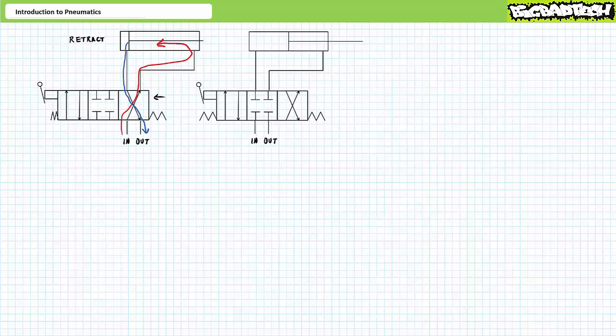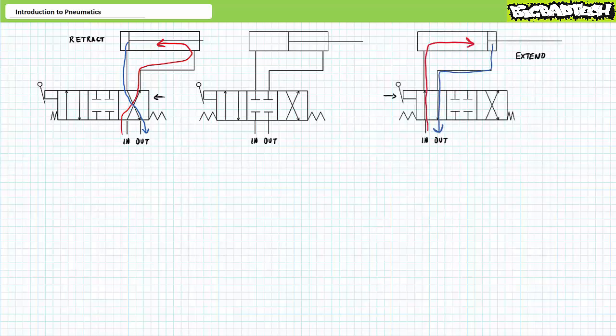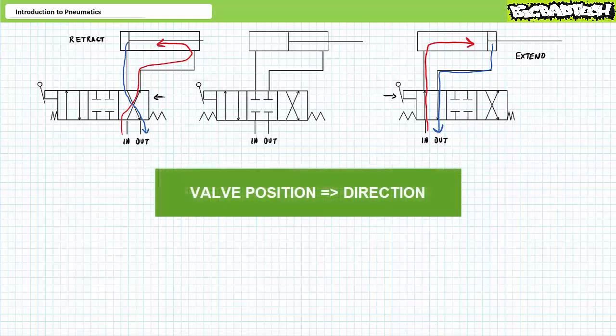The double-acting cylinder retracts. Conversely, when placed in the straight-through position, pressurized fluid is routed to the cap end, and the rod end is exhausted at low pressure. The double-acting cylinder extends. In summary, valve position determines actuator direction. This is true for both hydraulic and pneumatic systems.